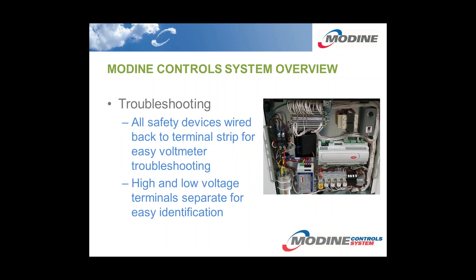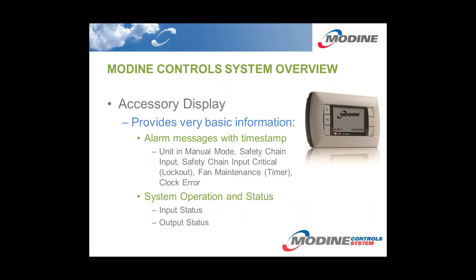Troubleshooting is extremely simple for these systems. Shown on the right is a typical water-to-water control panel. All of the safety devices are wired back to the terminal strip for very easy voltmeter troubleshooting. High and low voltage terminals have been separated for easy installer identification — the block on the top is the low voltage connections, and the block on the bottom right hand corner is all of the high voltage connections. An accessory display is available for purchase with the systems, mainly for very basic information: alarm messages with a time stamp, and system operation and status — basically just a confirmation of what they can see with their voltmeter, showing the status of the inputs and the status of the outputs.